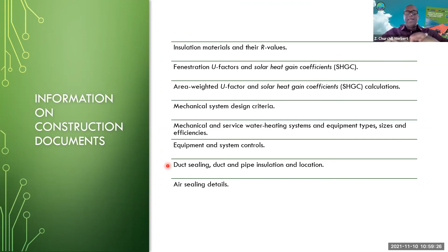Duct sealing, duct and pipe insulation and location, very important, because the project owner may spend an enormous amount of money buying the most efficient equipment, for example, the most efficient air conditioning system, but if your ducting system that transfers the conditioned air from one location to the other is not properly insulated, then you're defeating the purpose. The same thing for pipes. If you're distributing the fluids and they are not insulated properly, then you could miss the point in terms of being as efficient as intended. And finally, air sealing details.